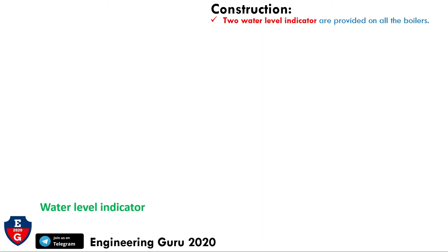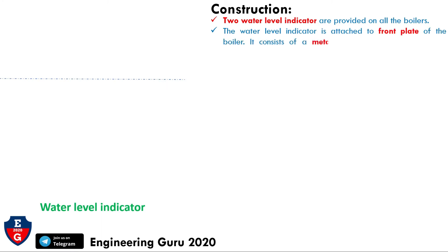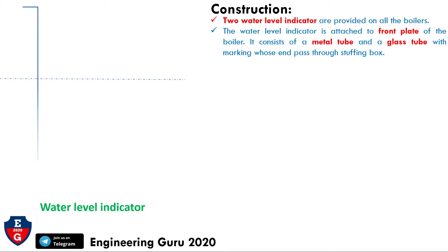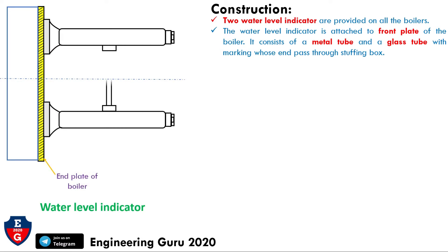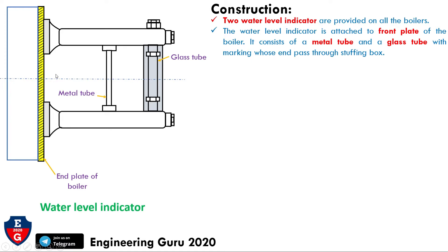Starting with the construction: two water level indicators are provided on all boilers. As seen in this figure, the water level indicator is attached to the front plate of the boiler. It consists of a metal tube and a glass tube with marking whose ends pass through the stuffing box. Here you can see the metal tube and the glass tube, and in yellow the end plate of the boiler. The glass tube is made of toughened glass so that it can withstand boiler conditions.